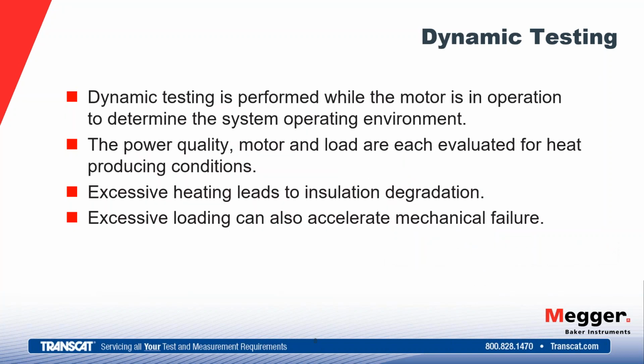The 5th of the big 5 that we want to talk about here is dynamic testing. Dynamic testing is performed while the motor is operating to determine the system operating environment. So it's not necessarily motor testing, but a collection: the power quality, the power being fed to that motor, the motor, and the load are each evaluated. Because the motor is only reacting to what the load is demanding, what it's requesting of the motor.